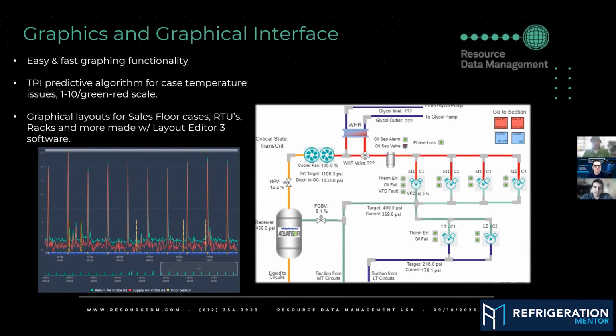We'll touch a little bit on TPI. That's our predictive algorithm for what a case is doing. It's a 1 to 10, green to red kind of scale that you can use, and you can actually alarm off of it. If your case is having an issue maintaining temperature, you can throw an alarm before you're even at an overtemp alarm. A lot of times when a coil ices up, you will be displaying issues with temperature in that case well before you're alarming. And you can use that TPI alarm as an indicator to get someone to look and see if a case has an issue.